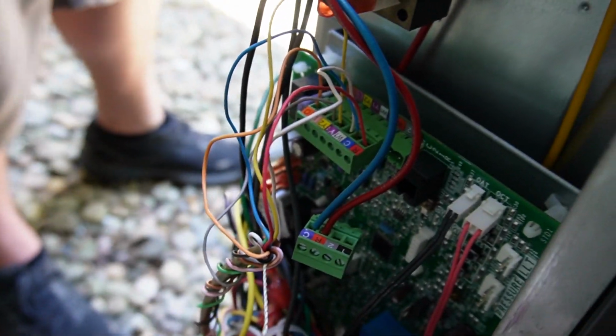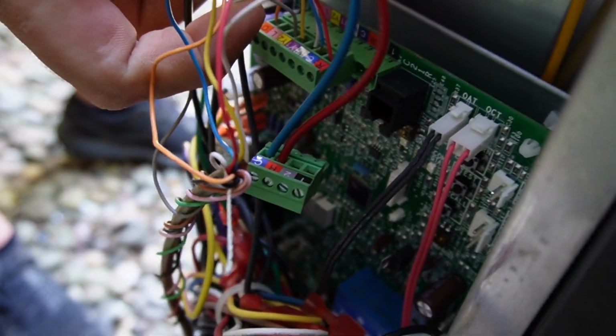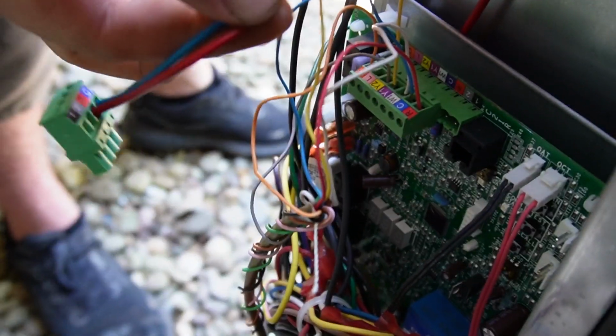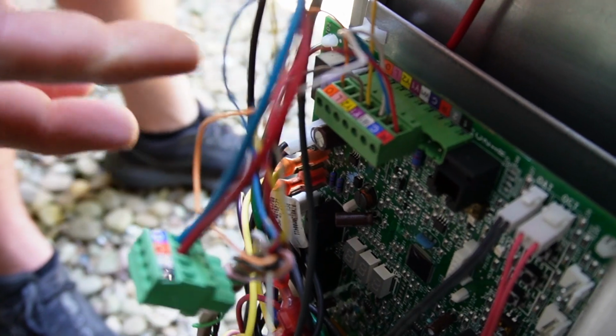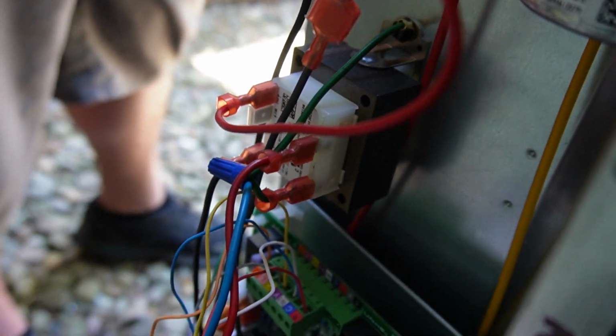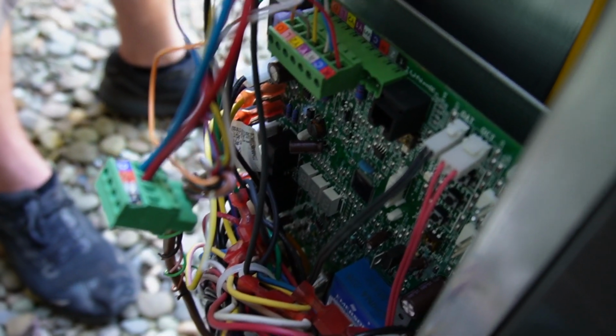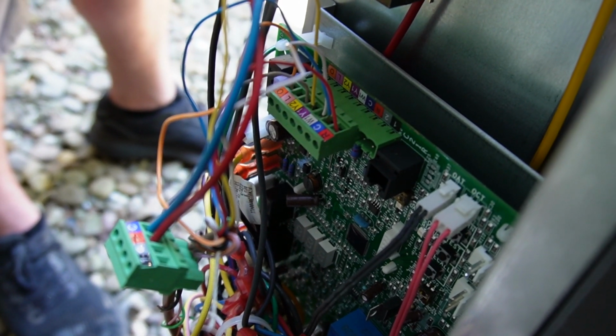So what do we have to say about this here? It is wired out here for two stage. They've just undone your comfort bridge plug, still with the transformer in it. So what we're gonna do is go back with the comfort bridge setup. Each stage will work individually, properly with the indoor unit.